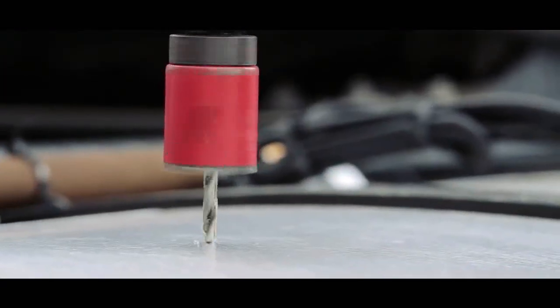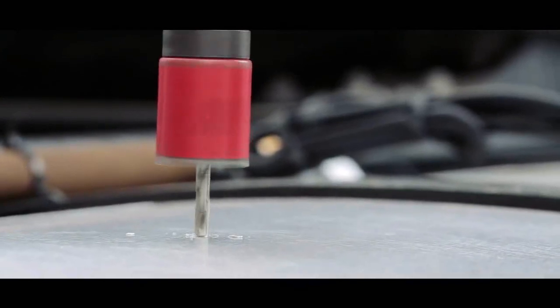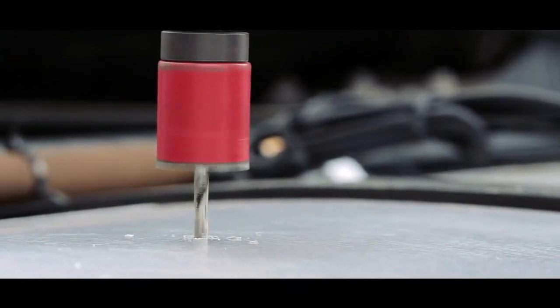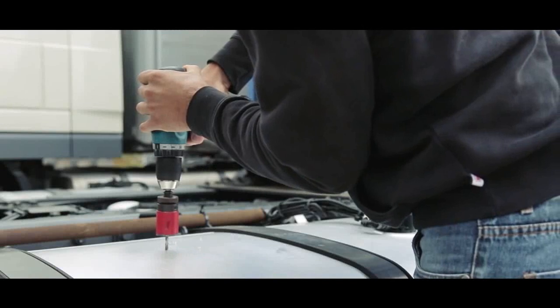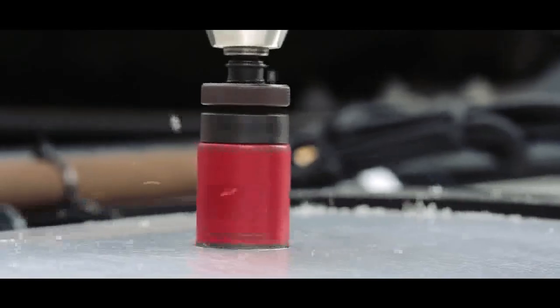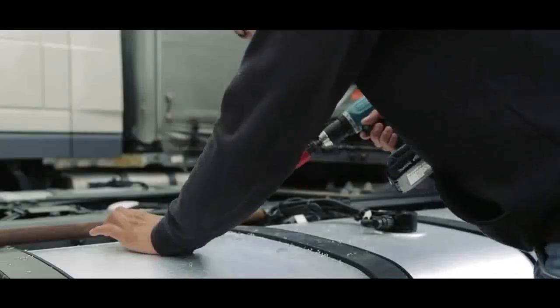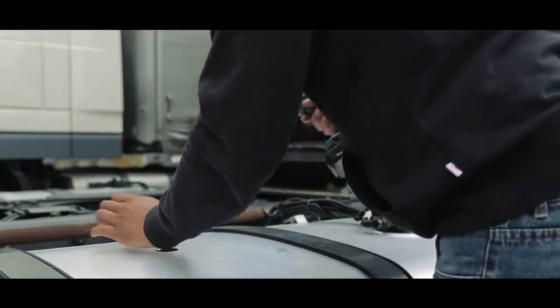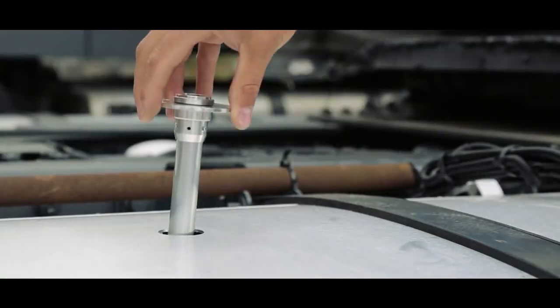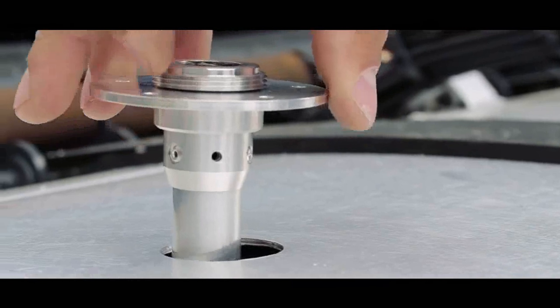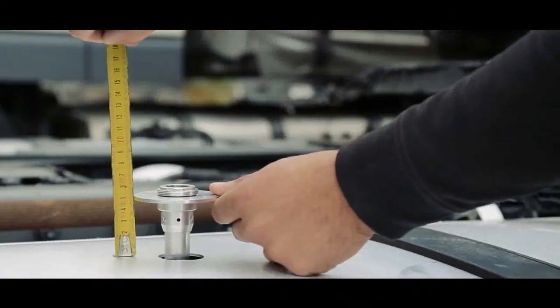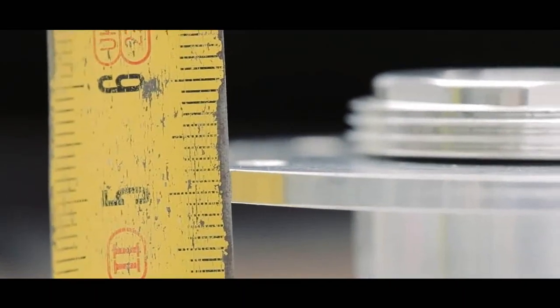If it is impossible to do it at the center of the tank, try to do it as close to the center as possible. Drill a hole that has a slightly larger diameter than the probe so that the flange will fit in. Try to prevent getting metal shavings into the tank. Put the probe into the tank through the drilled hole and measure the distance from the tank top to the top of the probe flange.